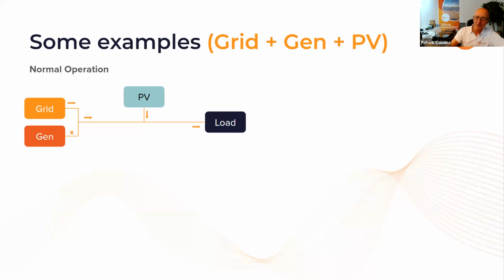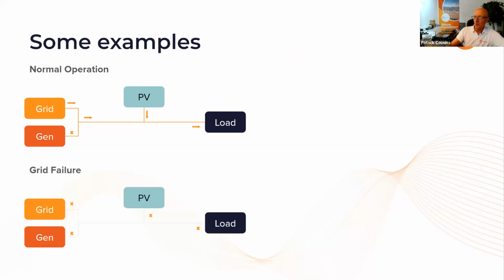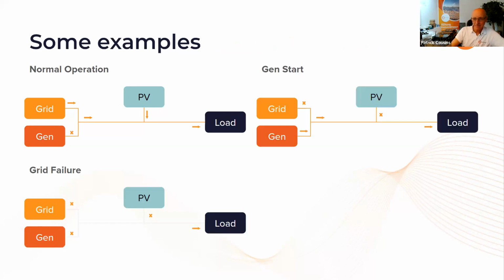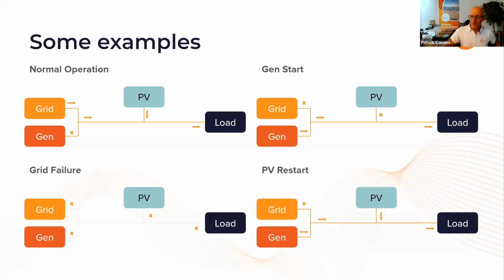So here's a typical beginning scenario. We have the grid running, the generator's off, the PV is working on the rooftop, and the load is being provided with power. If you go on to the next slide, you get a grid failure, at which point you can see that basically the PV turns off. At which point you need to tell the generator to turn back on. And when the generator goes back on, then after that, the PV will re-engage. Now, there are different versions of this, as I mentioned, but if the PV does re-engage, then you have to be careful that it doesn't backfeed into the generator. So you want as much power as possible from the PV, but you do not want to damage your generator by feeding it backwards into the generator system. So the load could be covered to a large percentage by PV. That reduces your fuel consumption, and you're fine. If we go on to the next slide, we're in another scenario.